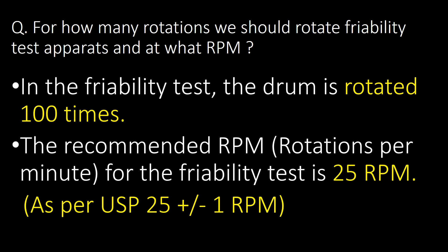Second question: for how many rotations should we rotate the friability test apparatus drum, and at what RPM? In the friability test, the drum is rotated 100 times, and the recommended RPM — that is, rotations per minute — for the friability test is 25 RPM.